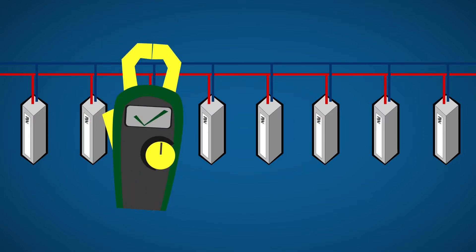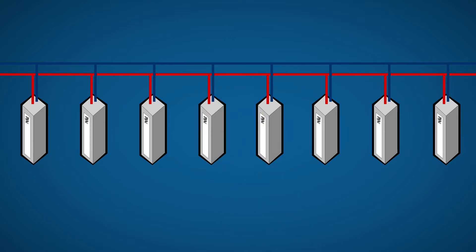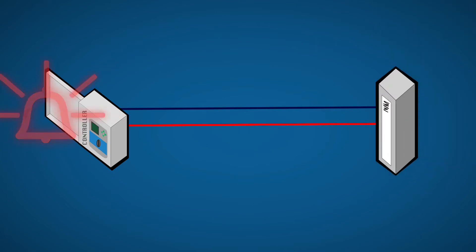Through a process of elimination, you can gradually track down the source of the issue. In some cases, the culprit will be a lightning damaged decoder. The controller will exit from the short alarm mode when the decoder is replaced.